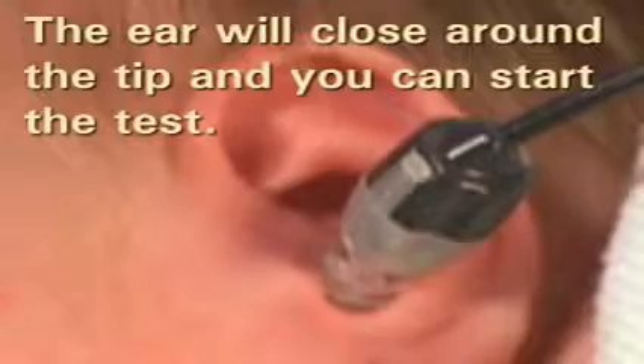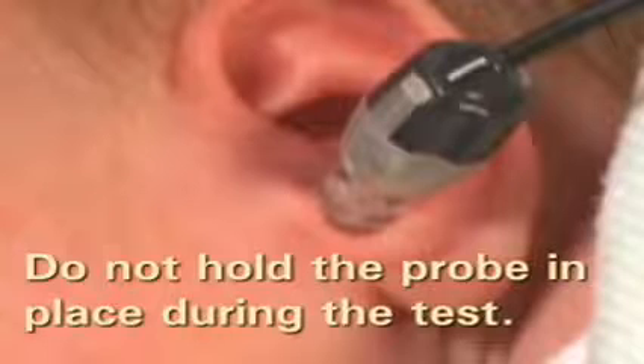Next, grasp the earlobe, gently pulling out and forward. While holding the ear in this open position, slip the probe tip into the ear canal with a slight twisting motion and release the earlobe. The ear canal will close around the tip and you will be ready to start the test. Holding the probe in place is not recommended since slight hand movements can generate noise and affect the test outcome.